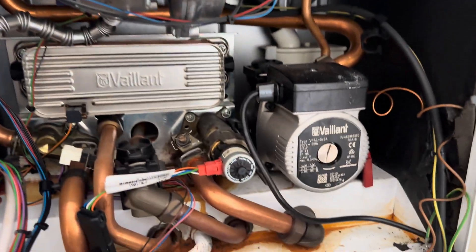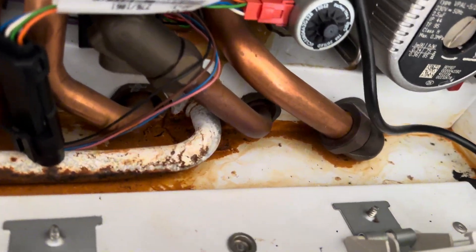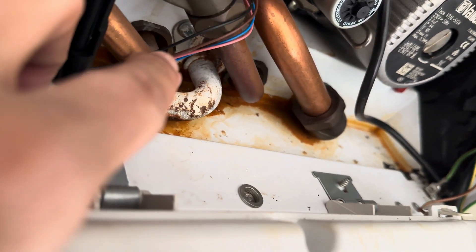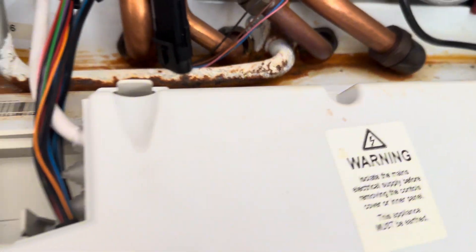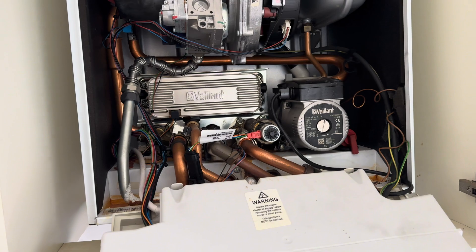See that gas pipe's corroded. There's two different types — you'll see a little D type shape here, and I've got to find the one that fits. I think it's that one — it's the flat one. Oh no it's not, it has the bracket underneath. Just rusted, hopefully I can get that out. So let's start with that pipe and we'll move on to the heat exchanger.